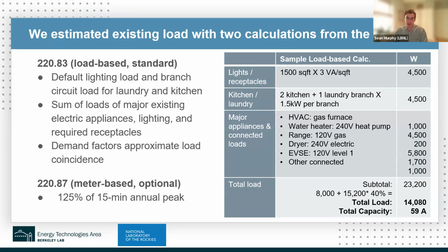The table on the right side of the slide illustrates this process, where we have a default assumption for the amount of power used per square foot with lighting, a default assumption for the power used for each branch circuit, then the nameplate ratings of the different loads in the home, and then summing those all together while applying that demand factor, which approximates the coincidence of those loads. The second method, Section 220.87, or the meter-based method, uses interval metering data. It estimates the existing coincident load as 125% of the metered demand from the previous year. I believe 15-minute or 60-minute load is eligible here. We used 15-minute data in our calculations.